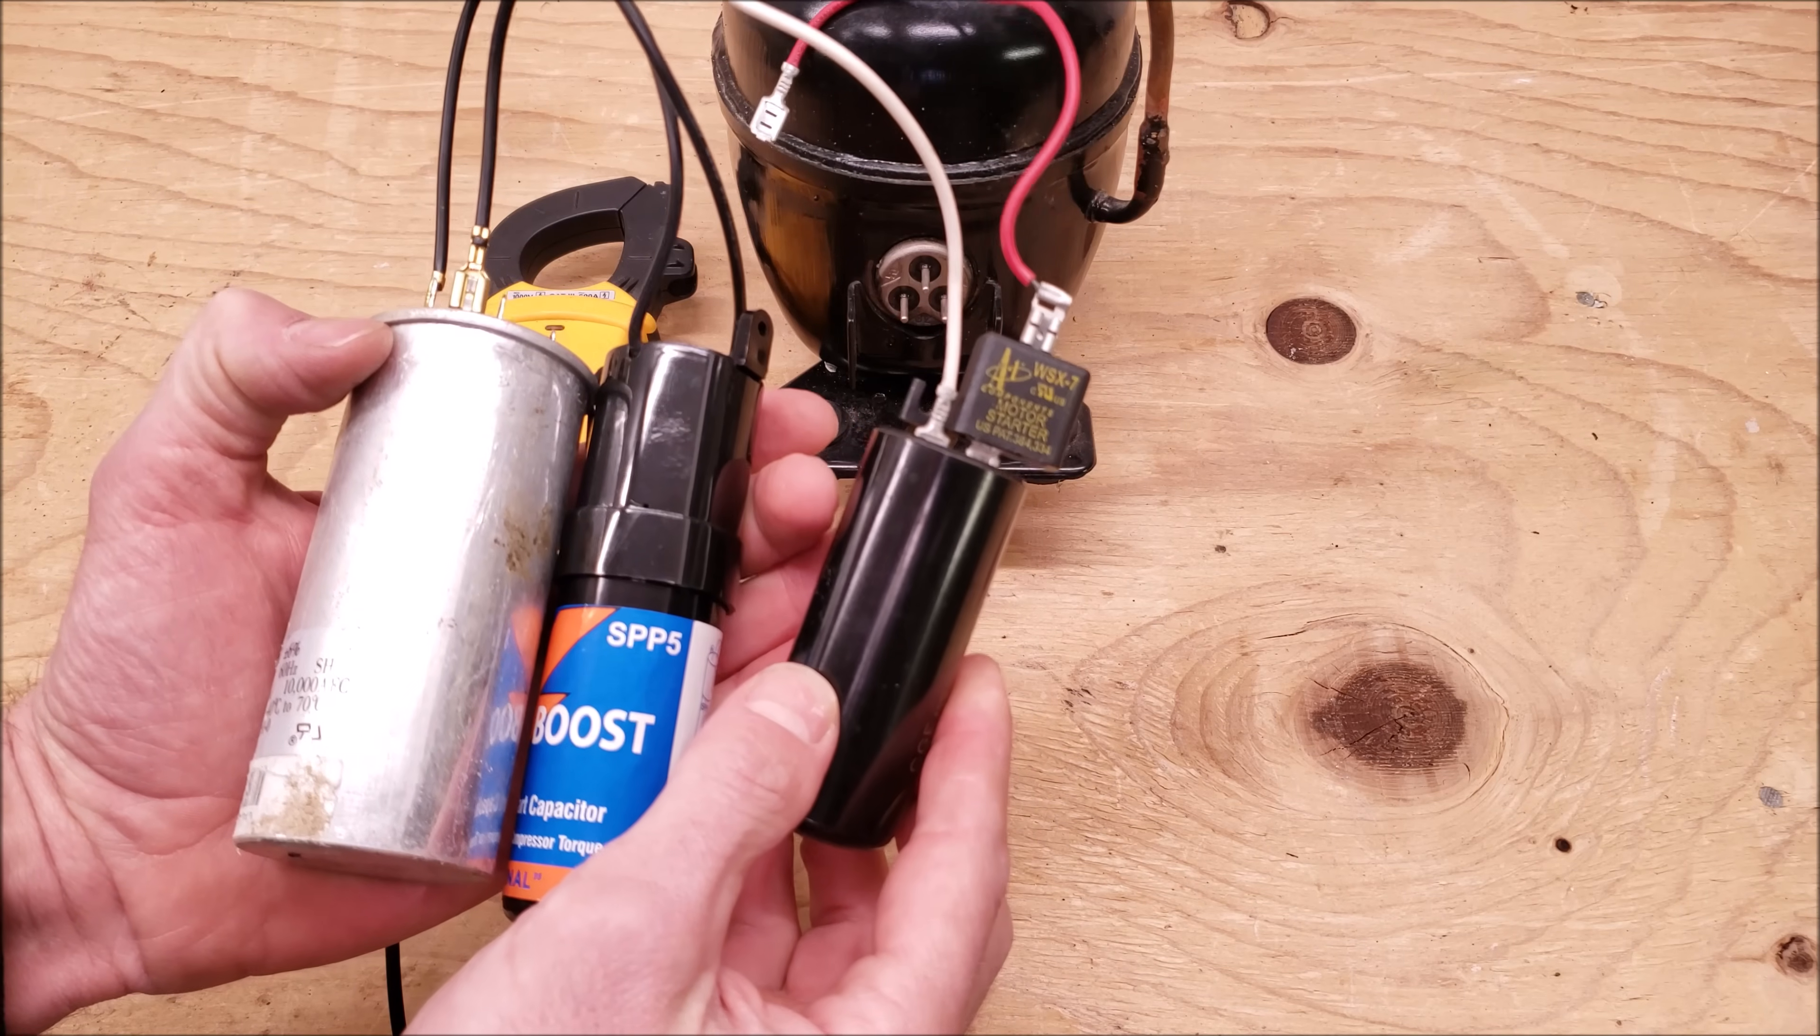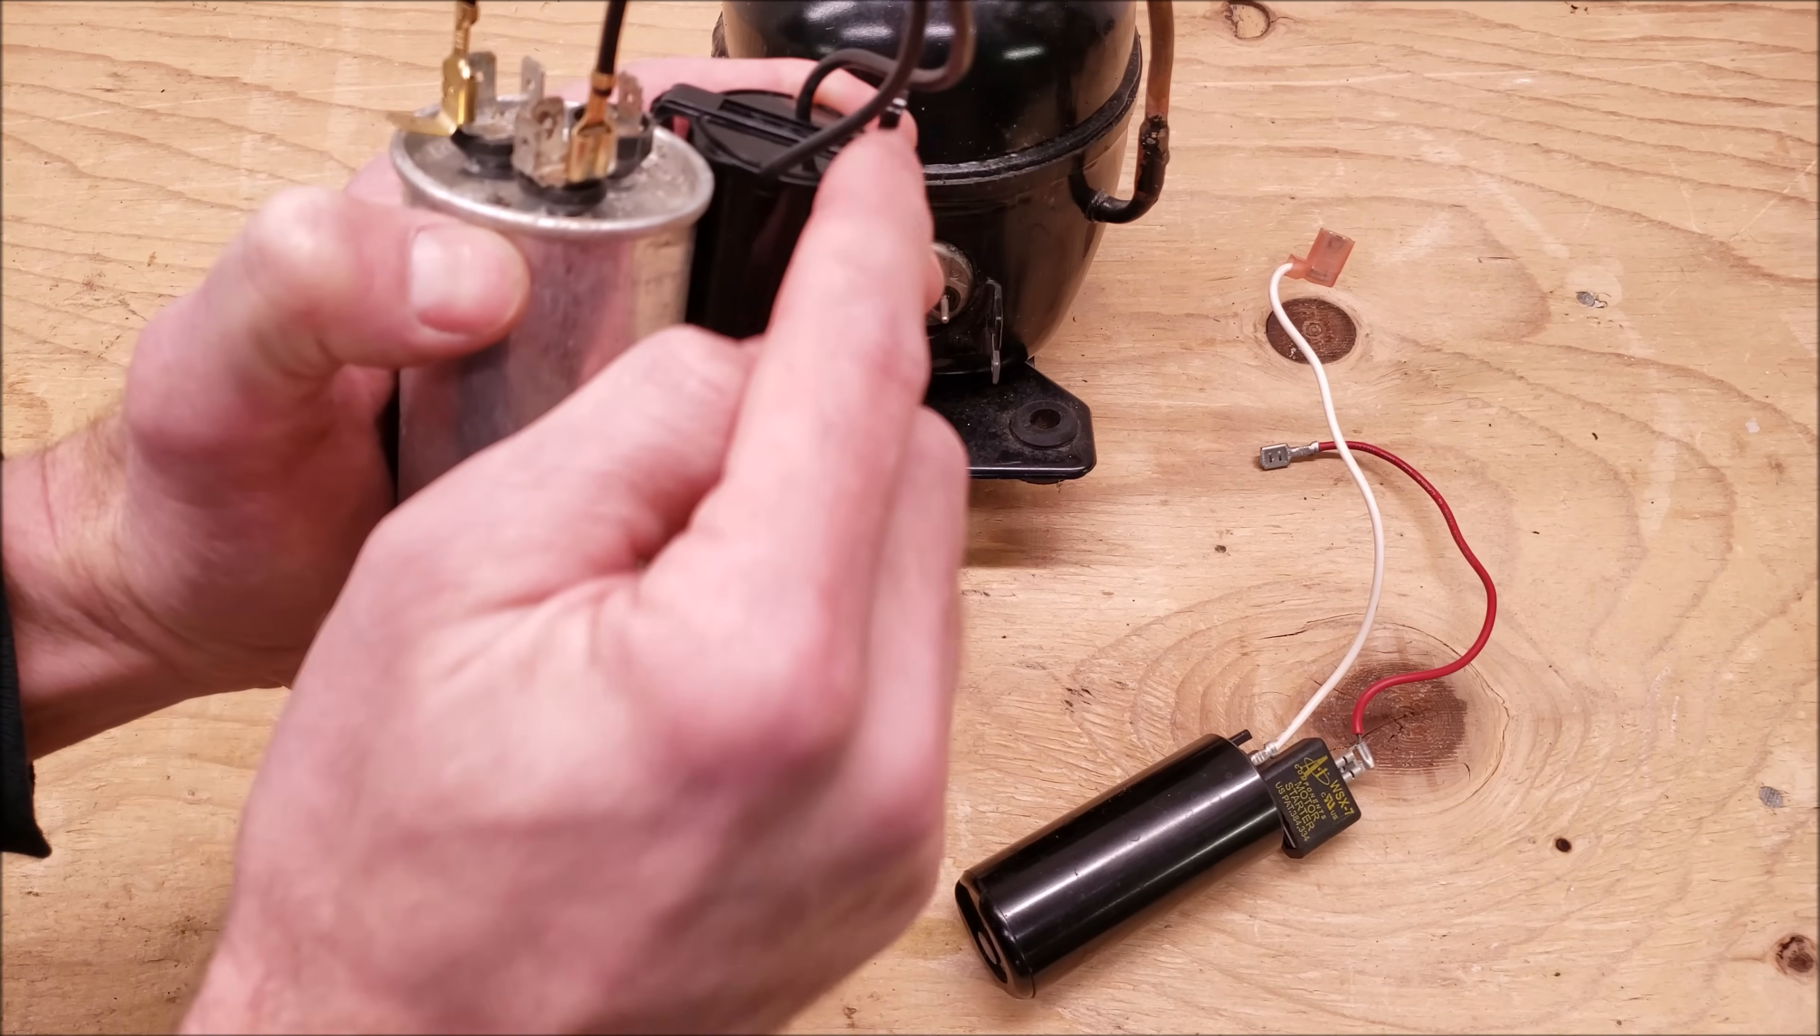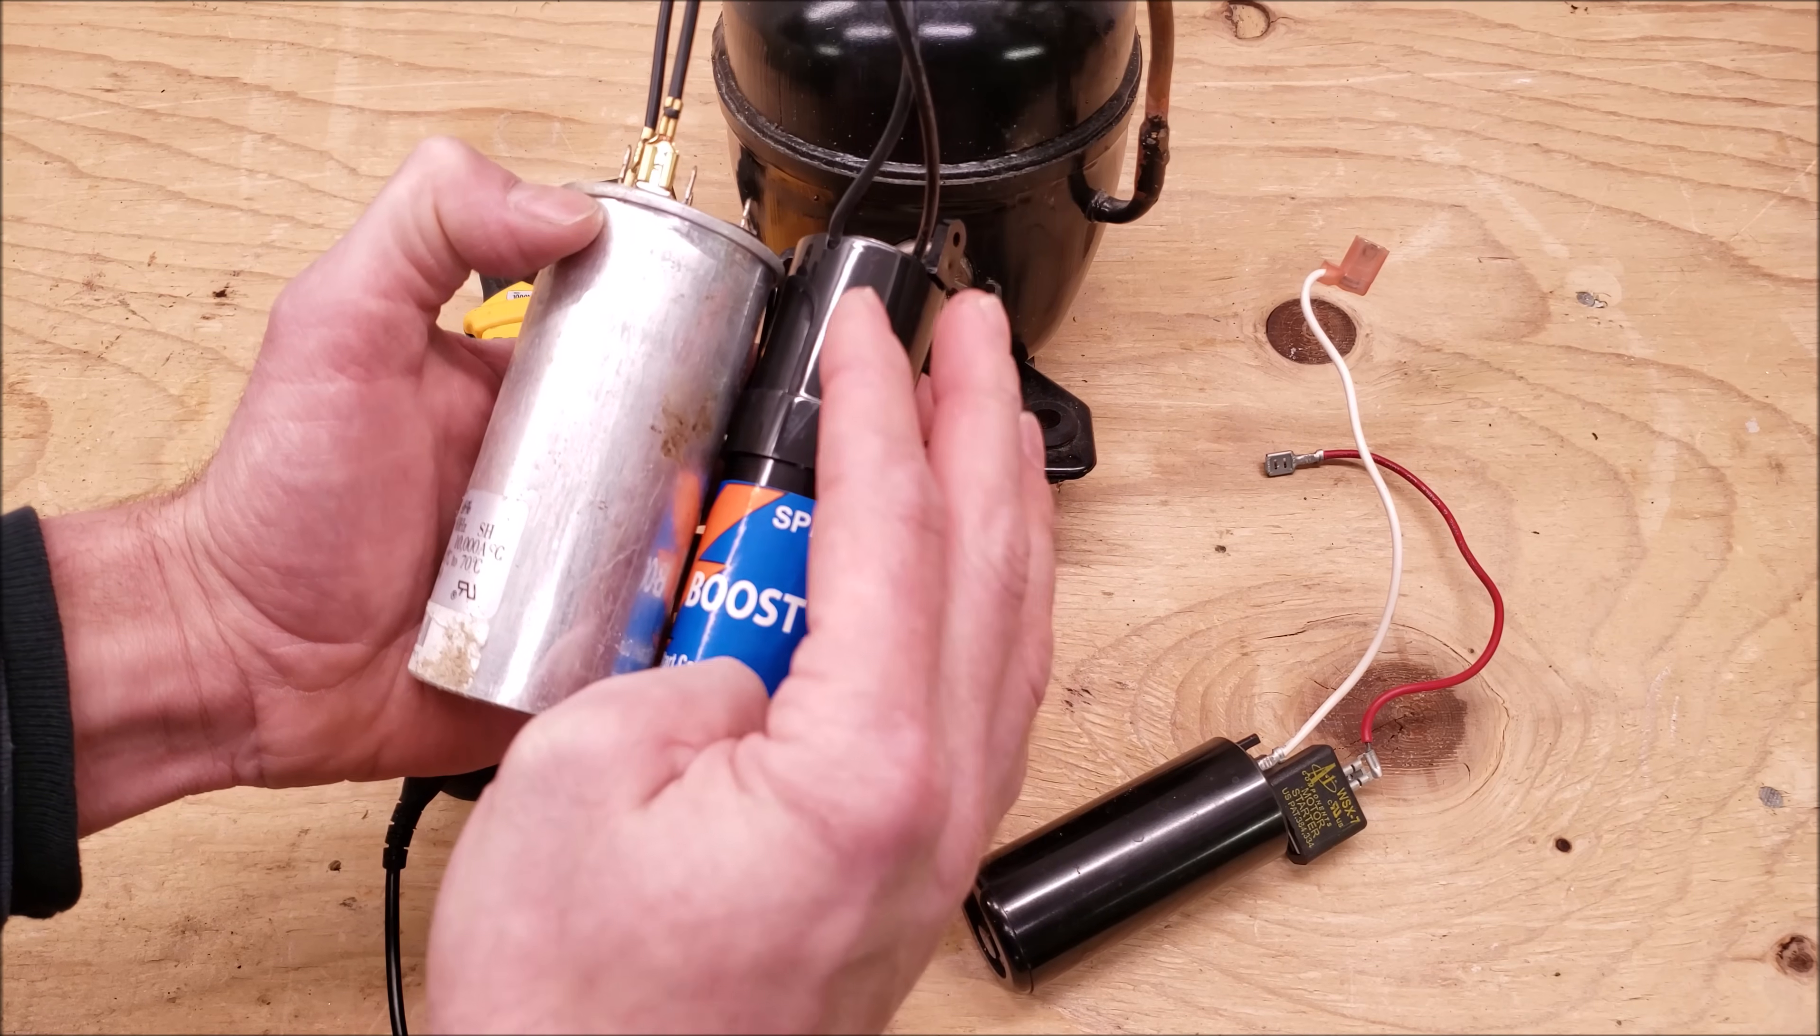In the case of the PTC thermistor used in the top of a start capacitor on like a hard start kit, basically what's happening is you have the wires connected to the C and also to the Herm. So the common and the Herm. And what's going to happen is it's going to take this start capacitor out of play once the compressor starts up.